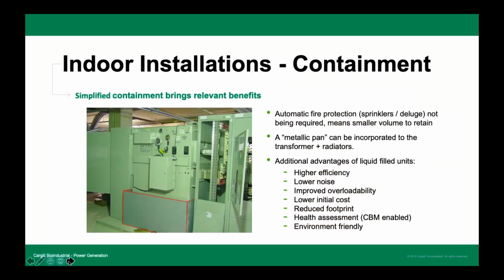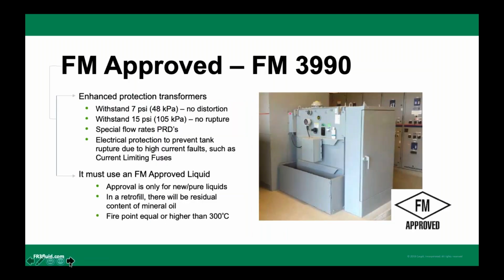One more example, you will find a similar indoor installation. In some places, they have made a rule that if by chance something happens to the transformer or some leakage comes, there should be a tray below the transformer. That's typically an American design. You will find every transformer has a small tray at the bottom, so that if there is minor spillage during repair or maintenance, it gets accumulated in the small tray. Or you can say secondary containment. Let's move on.